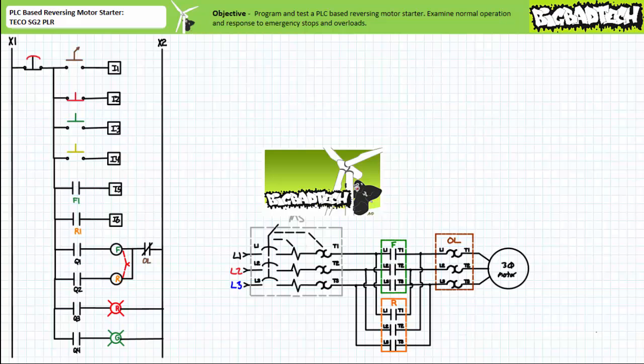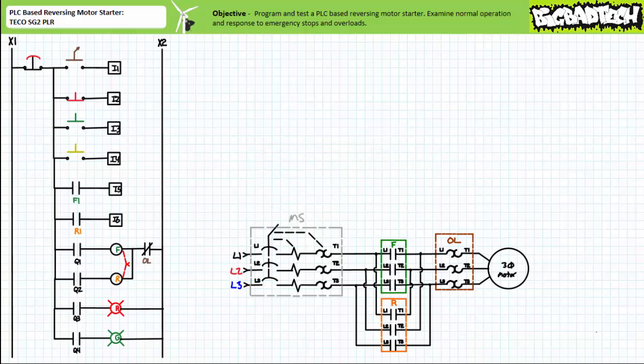A reversing motor starter as implemented using traditional hardwire relay-based ladder logic uses paired contactors wired such that the phase sequence of the forward contactor initiates operation in one direction and the other in reverse. It is vitally important that both contactors are never simultaneously closed, as this would constitute a phase-to-phase event. Reversing motor starters customarily employ degrees of interlocking to prevent this: mechanical interlocking prevents simultaneous physical closure, electrical interlocking prevents simultaneous energization of coils, and push-button interlocking deselects the opposite mode any time one mode is asserted. Plugging is an instantaneous reversal of rotational direction, bypassing a stopped intermediary state.